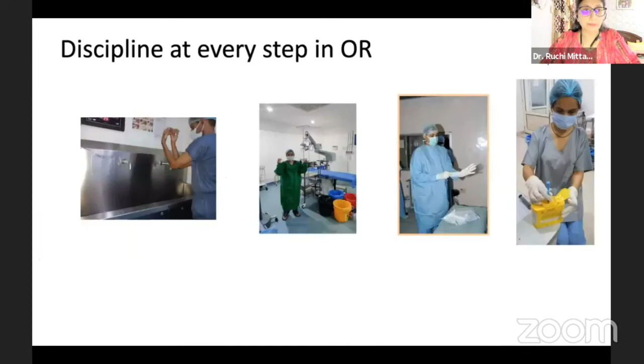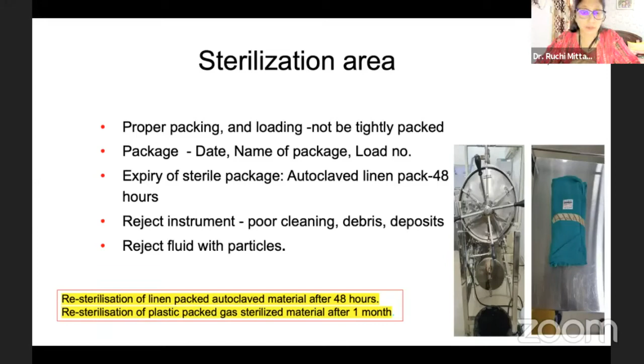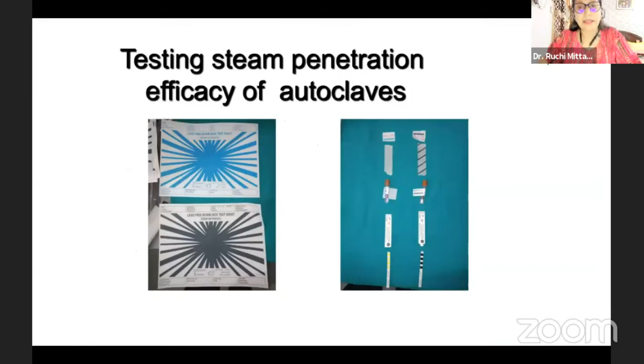Coming to the sterilization, proper packing and loading is recommended. The package should be properly dated, with the name of the package and the load number. If the package has been autoclaved, after 48 hours it needs re-autoclaving if it has not been used. Reject the instruments showing poor cleaning, debris or deposits, and reject the fluids with particles. These are the indicators which we use for testing the efficacy of autoclaves.